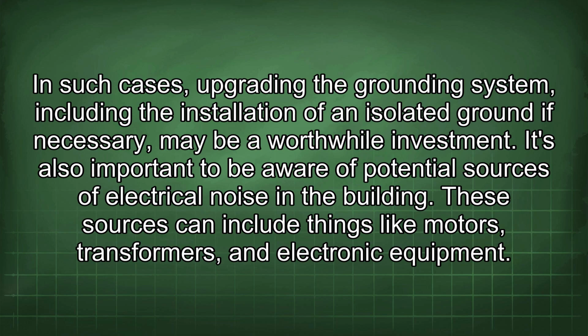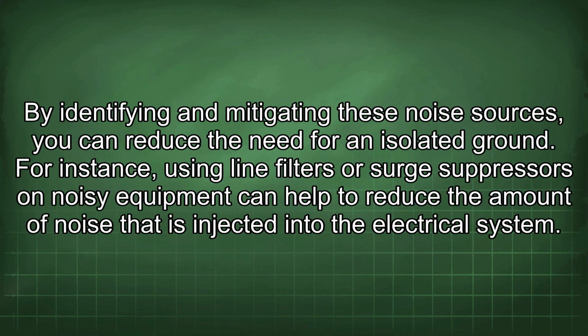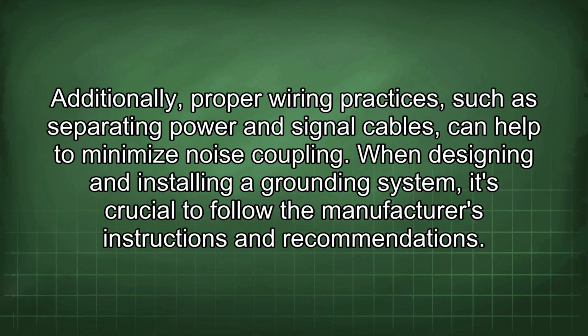These sources can include things like motors, transformers, and electronic equipment. By identifying and mitigating these noise sources, you can reduce the need for an isolated ground. For instance, using line filters or surge suppressors on noisy equipment can help to reduce the amount of noise that is injected into the electrical system. Additionally, proper wiring practices, such as separating power and signal cables, can help to minimize noise coupling.